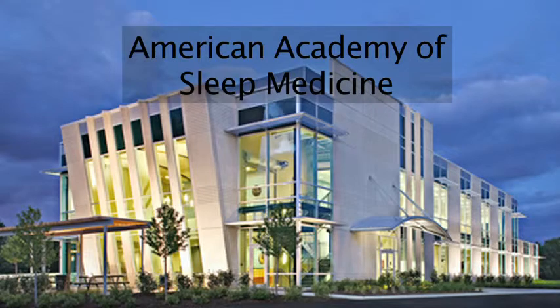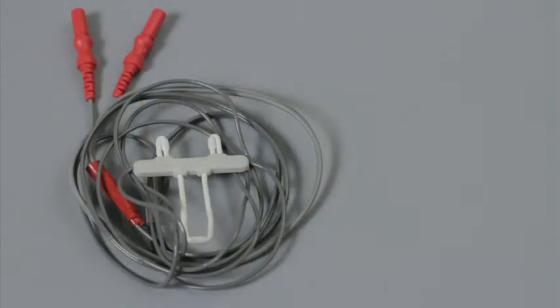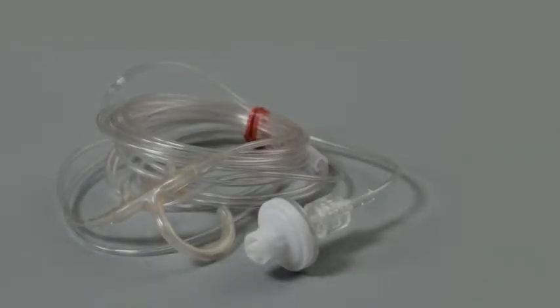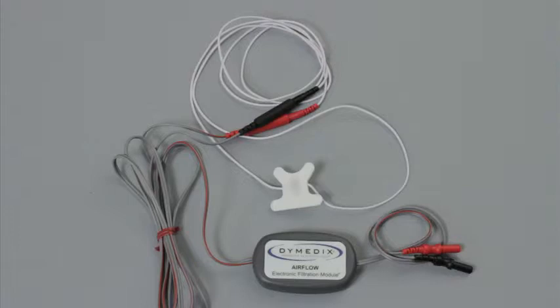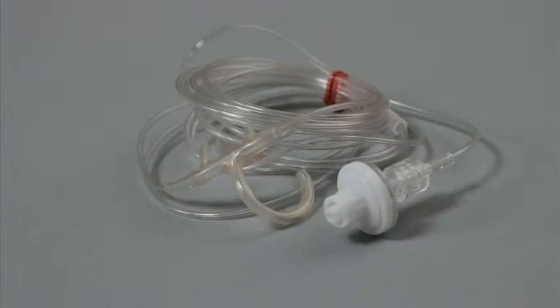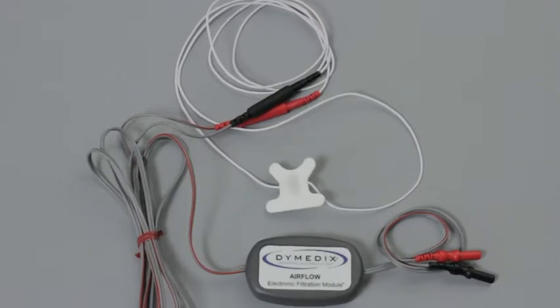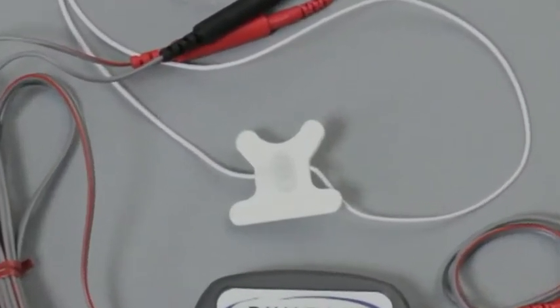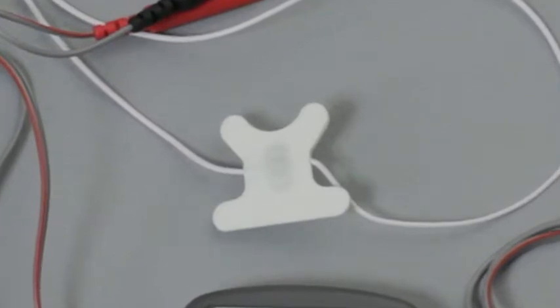The American Academy of Sleep Medicine, the AASM, recommends the use of therms for the detection of apneas and air pressure transducers, or APT, for the detection of hypopnea. APT is the other traditional technology used for airflow in a sleep study and utilizes a cannula. More sensitive than therms, the air pressure transducer does not detect apnea as well because it is not linear to airflow, and per the recommendations, both therms and APT are needed. PVDF is linear to airflow and will detect both apnea and hypopnea equally well without the need for two sensors. Unlike APT, it does not utilize a cannula, which can become dislodged or clogged with bodily fluids. As we will show later in this presentation, placement of the Dymedix PVDF-based airflow sensor is very much like a peel-and-stick Band-Aid. No prongs to go up the nose, so there is greater patient comfort.